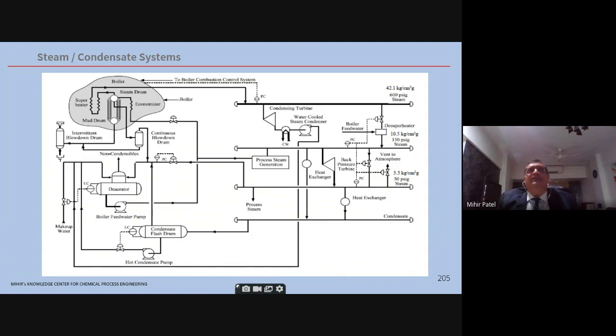On the right, you see the desuperheater taken to the next level of steam. From the next level, you can go to the heat exchangers, which are the actual end users, from where condensate comes out. You can have a back pressure turbine to produce power also. Again, you can have a PRDS assembly, what is called pressure reducing desuperheating station, to go to the LP level. From the LP level, again, you can go to heat exchangers and produce condensate. Condensate goes back to the flash vessel, the condensate flash drum, and then back to the deaerator.